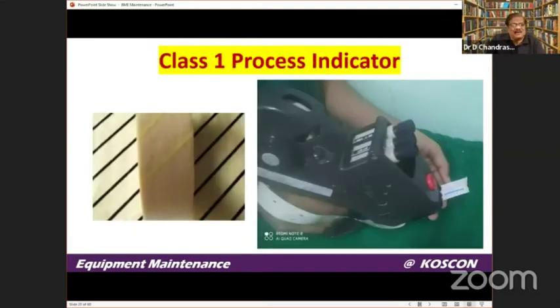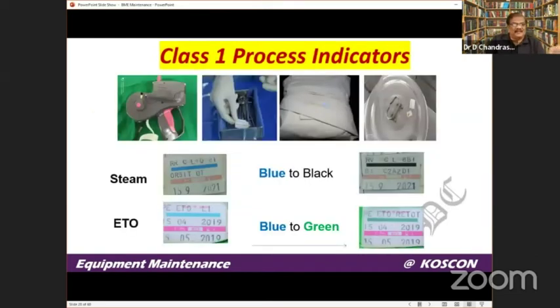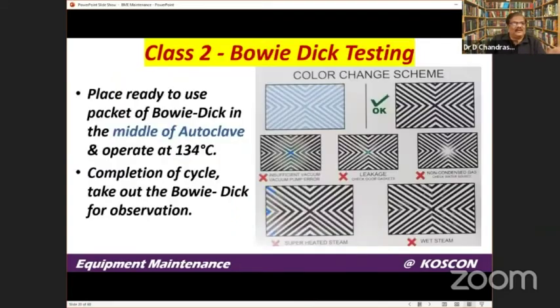Class 1 indicators are only process indicators—they show the machine has been switched on and off, with just a color change, and they can have an expiry. You see the change from blue to black for steam, and blue to green for ETO. Here the correct one is on top; in other failed cases, you see dull colors or no black line at all—these are failures.